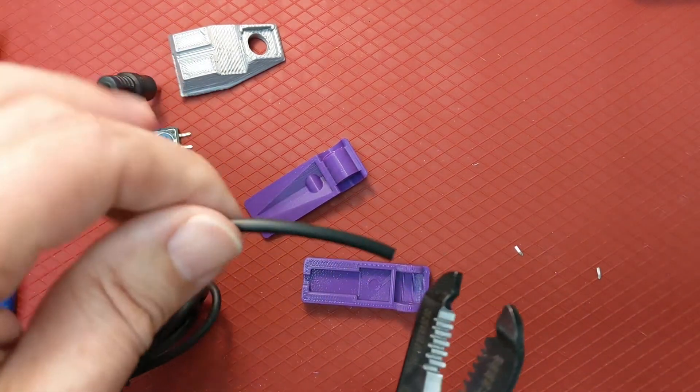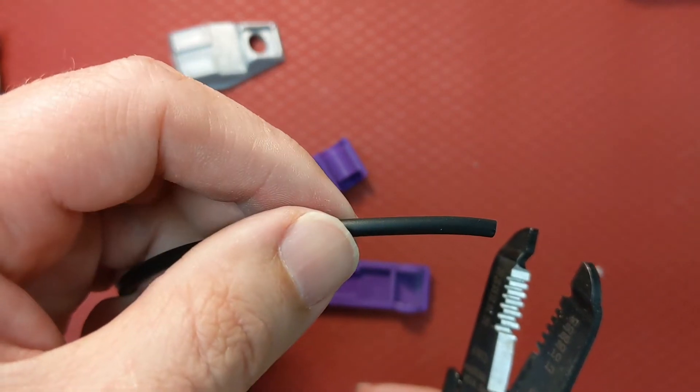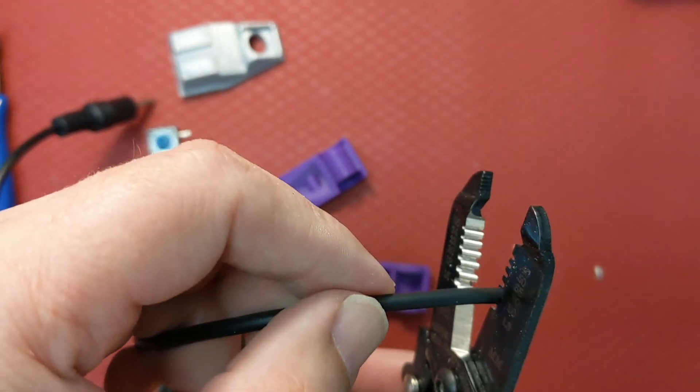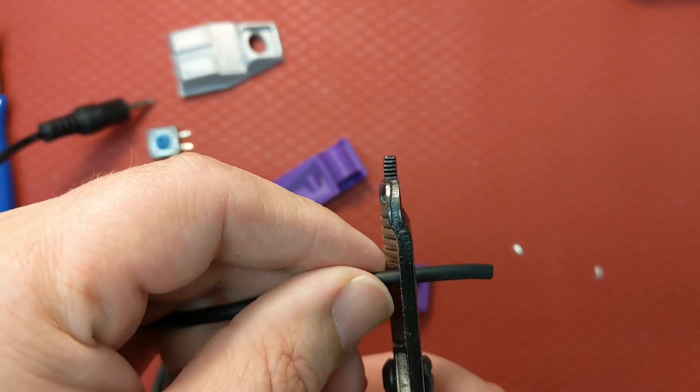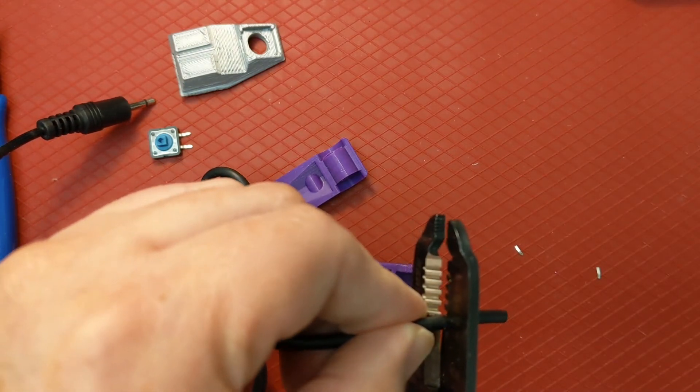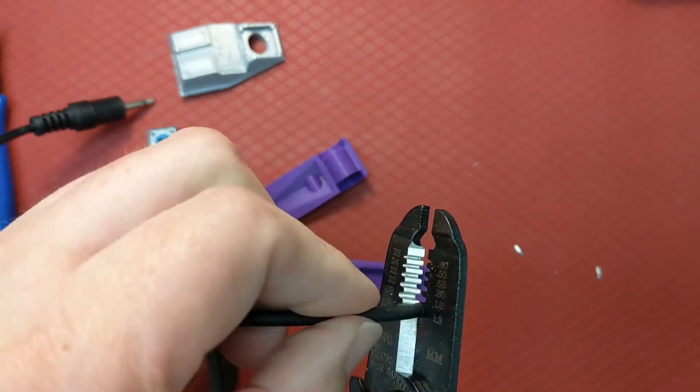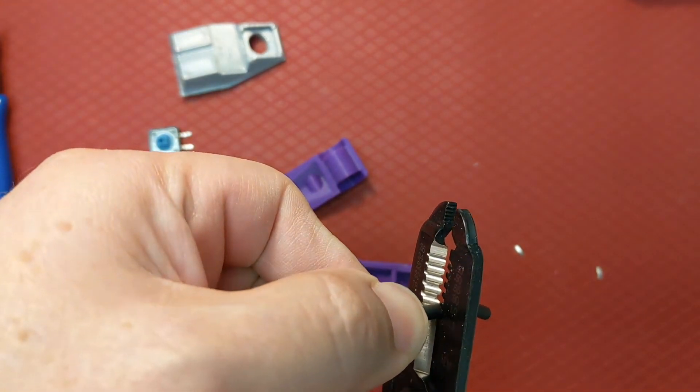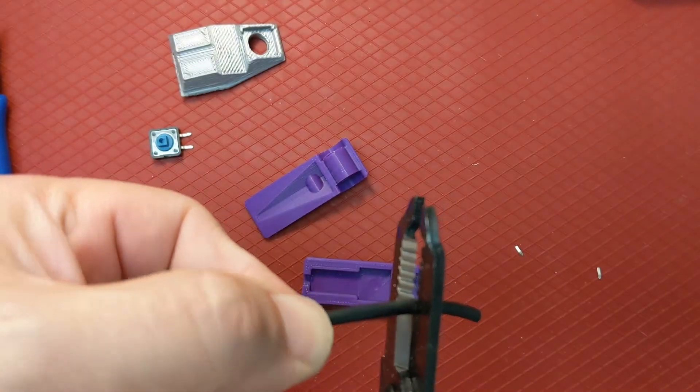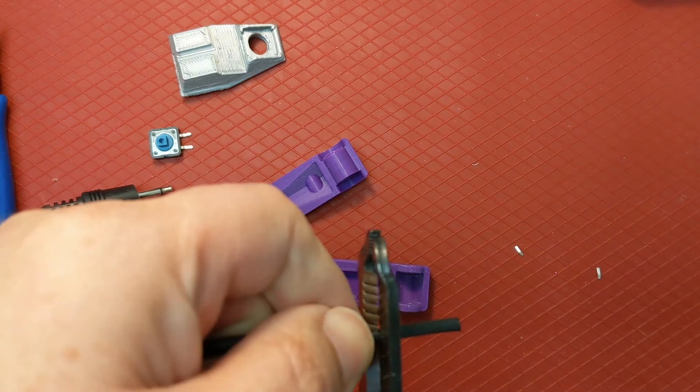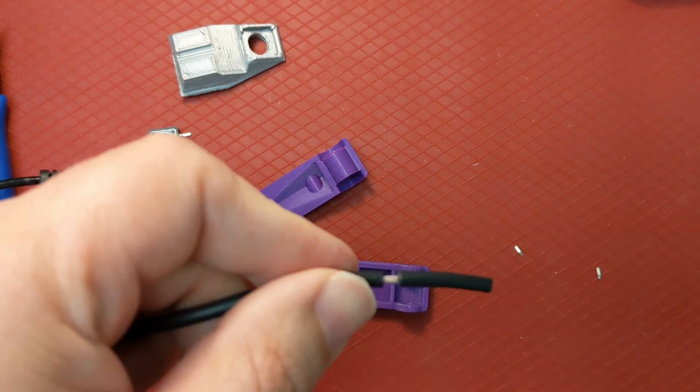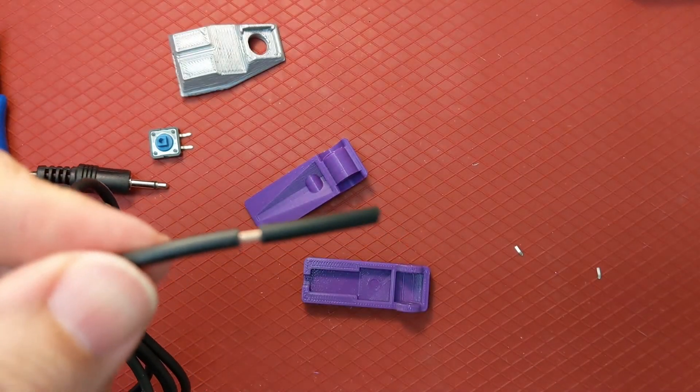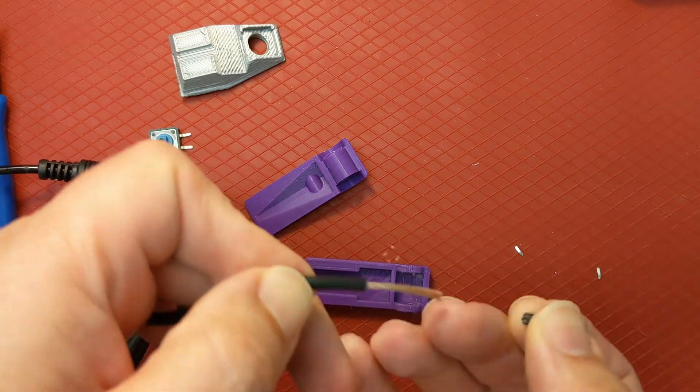So next thing you have to do is strip back the insulation. That's about two centimeters you need to take off. You can use the largest hole in the wire stripper, but you have to be a little careful. Don't push it all the way in. Just gently nibble away at it. You'll notice it slowly cuts through and leaves a sharp cut in the insulation.